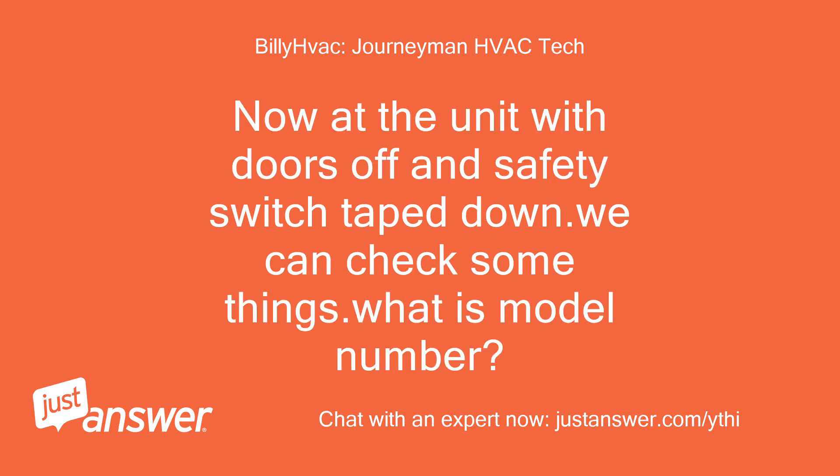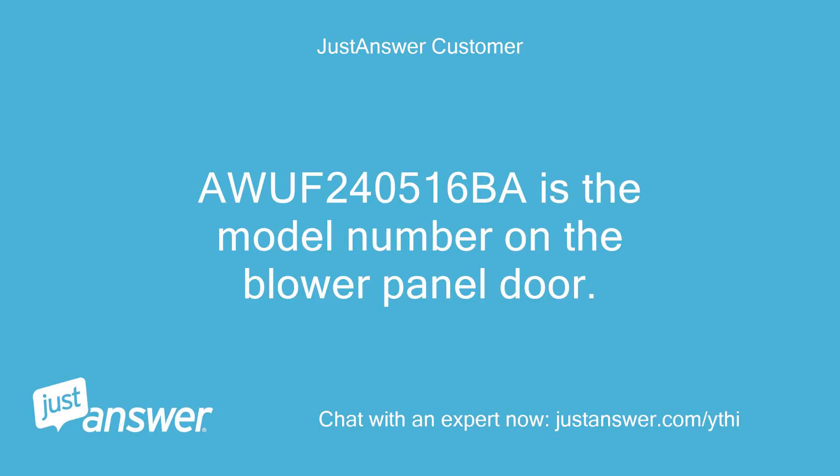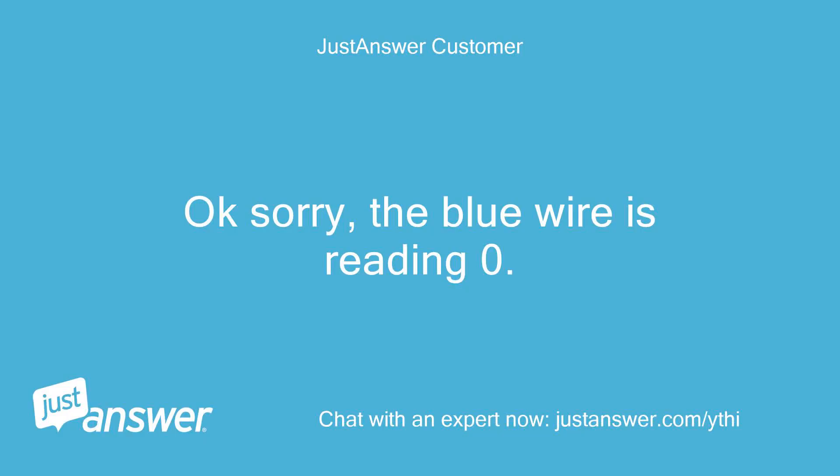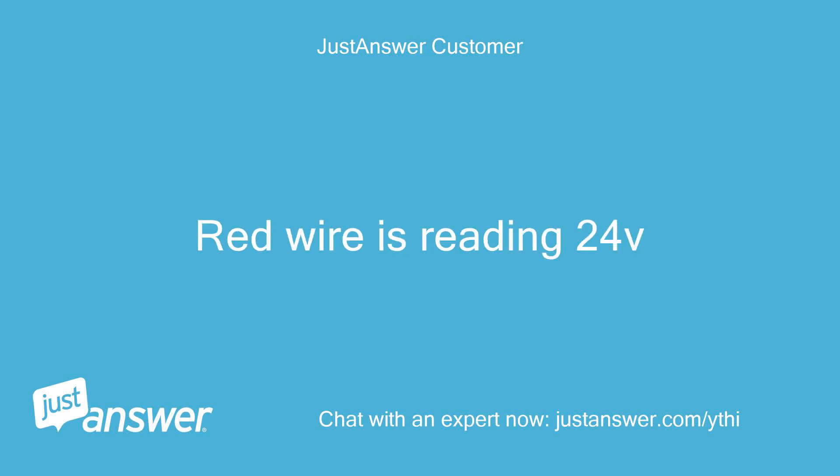Now at the unit with doors off and safety switch taped down, we can check some things. What is the model number? The model number on the blower panel door is AWUF240516BA. Thank you. You mentioned the transformer was hot — do you know if we have 24V between the red wire and the blue wire that the thermostat wires are attached to? The blue wire is reading zero; the red wire is reading 24V.